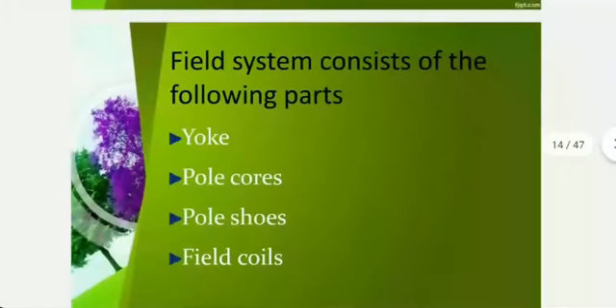One thing I forgot to tell you is that the poles' cross-section in theory should be rectangular or some well-known shape. In practice, we expand the cross-section at the end and make it bigger to get better efficiency. That expansion is called pole shoes. I'll show it to you maybe in some other pictorial diagram later. Pole shoes essentially mean a much bigger cross-section compared to the cross-section of the actual pole. It helps in improving the coupling to the rotating conductors, and that improves the efficiency.